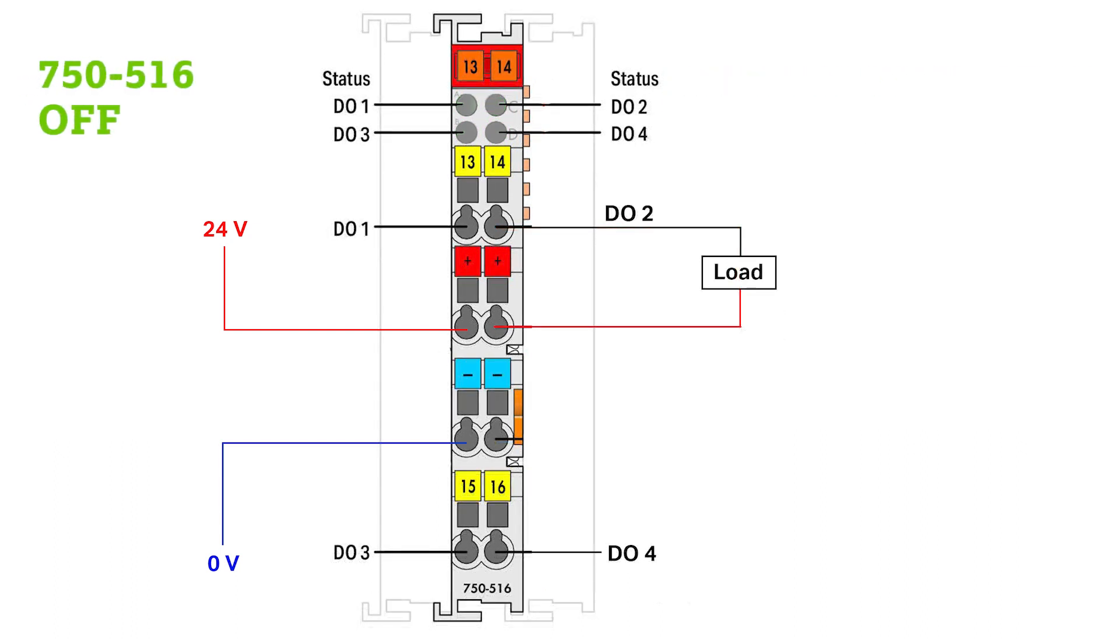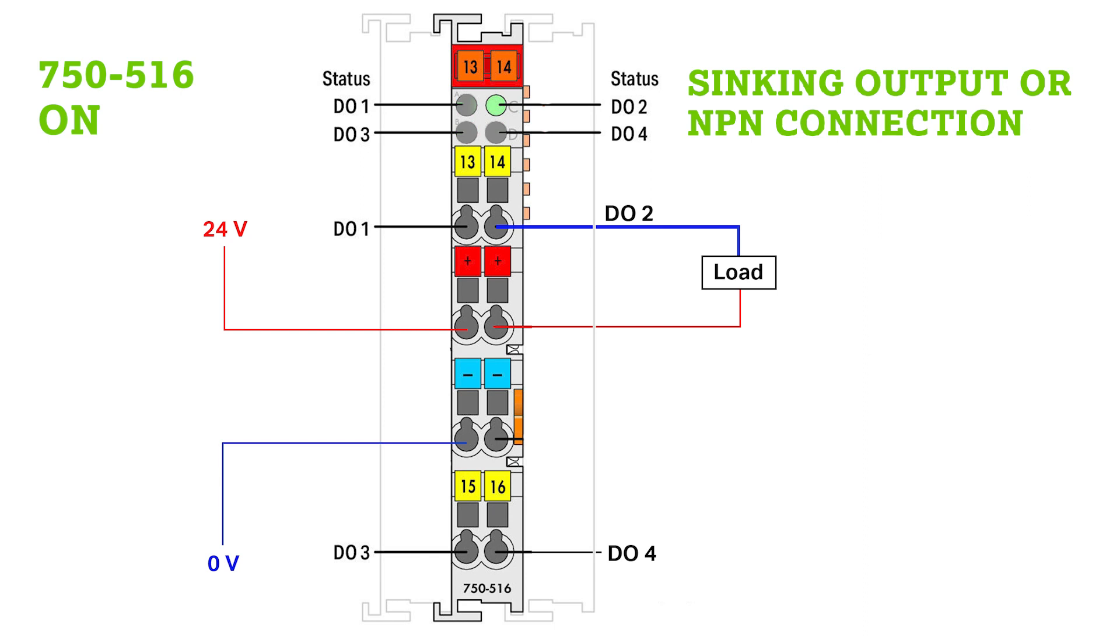WAGO's low side switching output module, the 750-516 for example, provides and switches the 0V ground as the output of the module coming from your load. This is also referred to as a sinking output or an NPN connection.